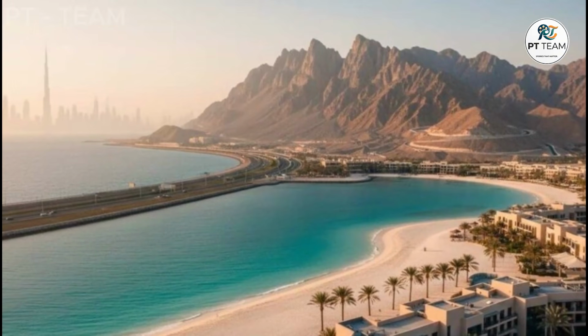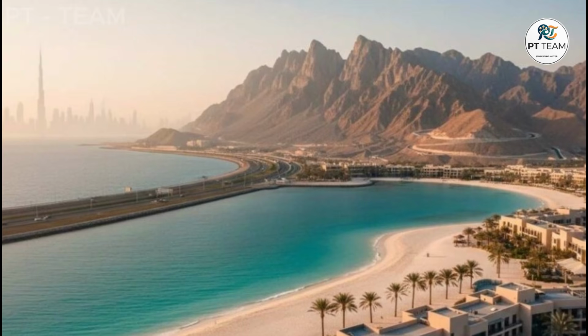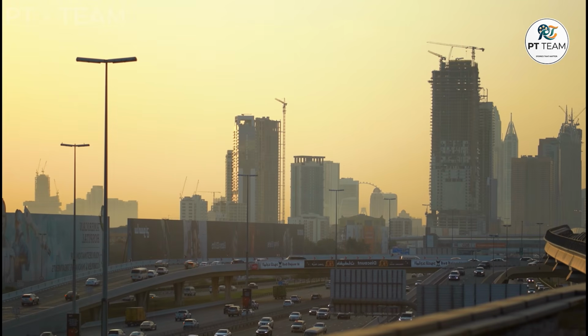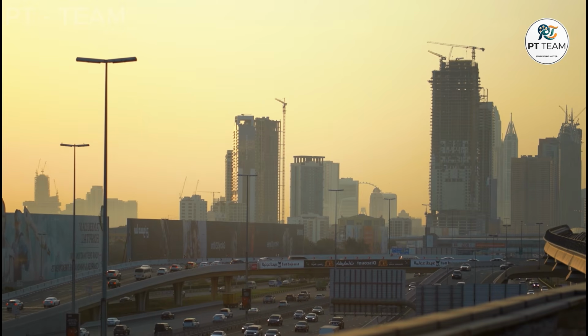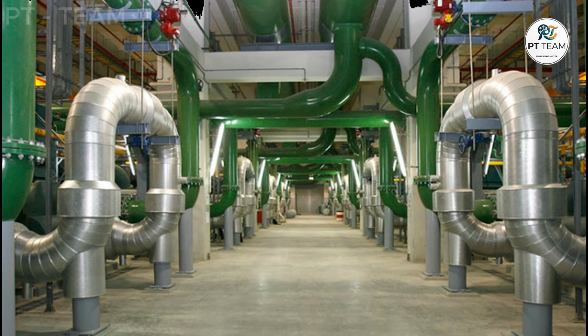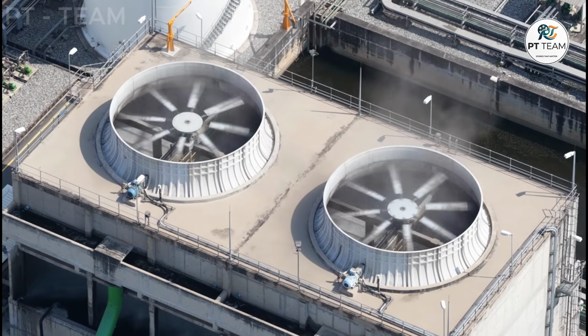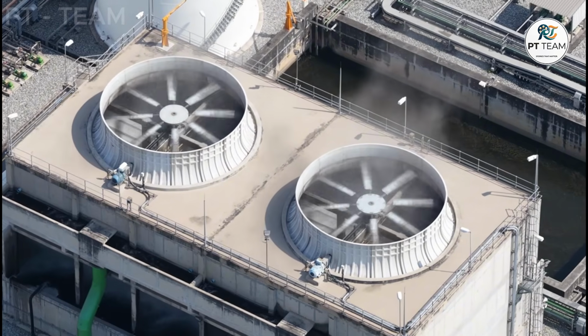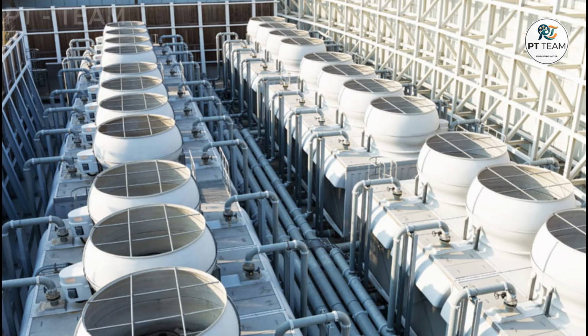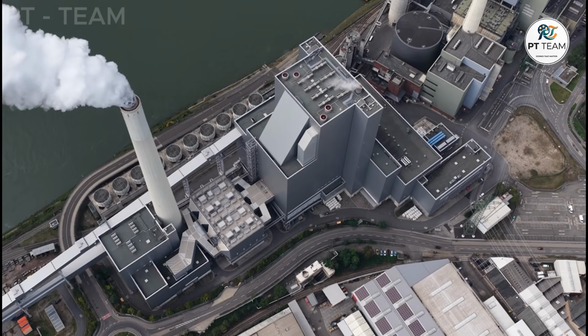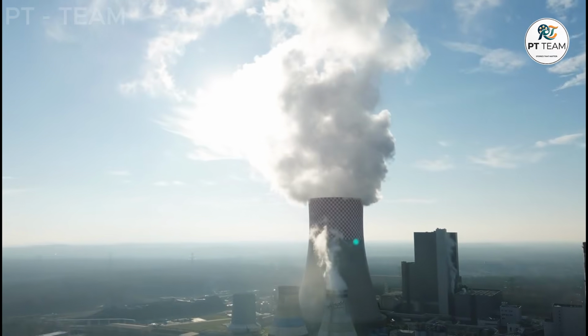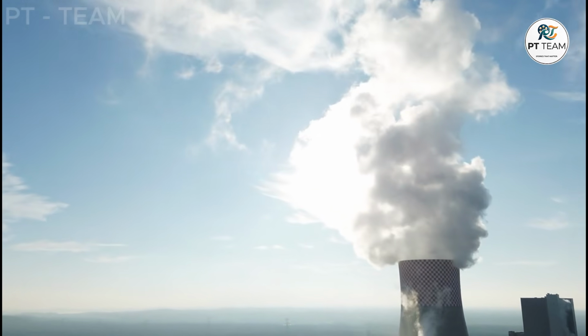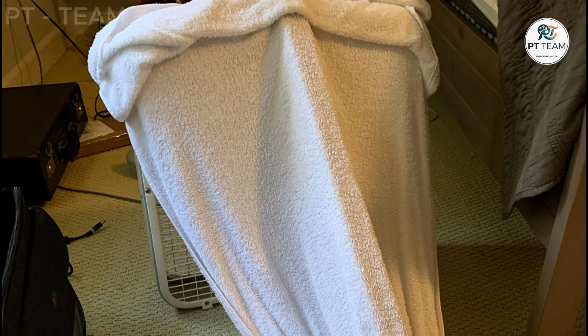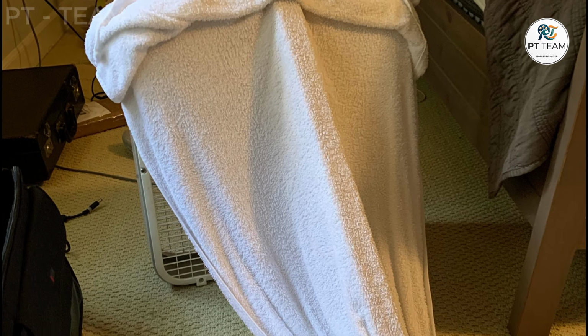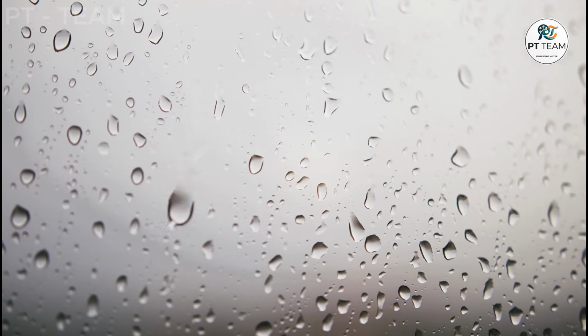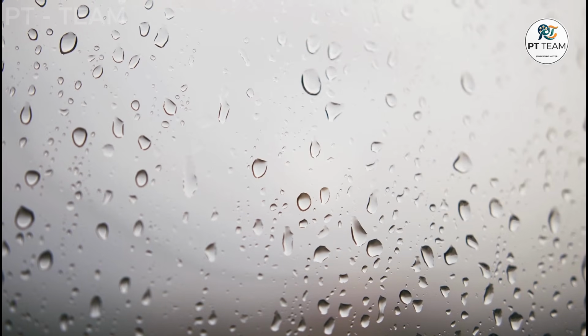And Dubai's coastal desert atmosphere can make one critical part of that rejection process significantly more demanding than most viewers might expect. When the central plant extracts heat from the returning water loop, it must eventually release that trapped thermal energy directly into the surrounding atmosphere. Many large-scale district cooling facilities rely heavily on towering cooling towers to accomplish this, and these towers reject heat largely through the physical process of evaporation. If you place a wet cloth in front of a rotating fan in a room filled with extremely dry air, the moisture evaporates quickly and the cloth cools down rapidly.